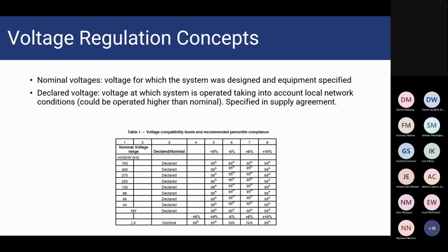So that's why it's important, when you set up a power quality recorder and a measurement point for recording, that the declared voltage is correctly defined. That way, when you compare your voltage regulation on different meter points or different measurement points, you can compare the values with each other, because you set it for the same declared voltage.